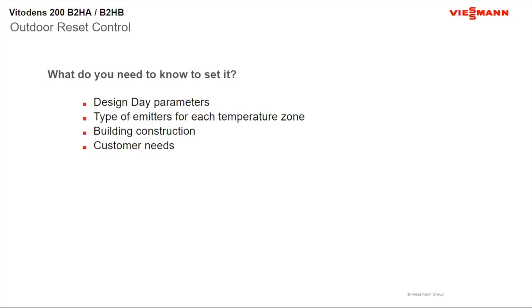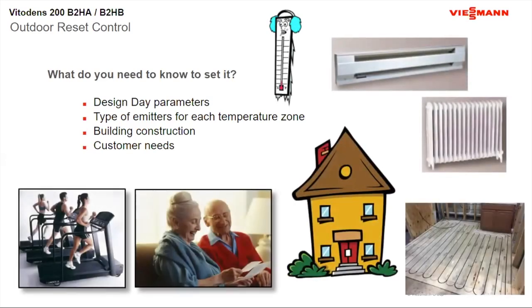The design day parameters to consider: what was the house originally designed for — or for new construction, what do your state requirements say? What type of emitters are you using and what supply temperatures will you need? Looking at baseboard manufacturer rating charts, temperatures go down to 118°F — you can heat a house with 118°F water if you have enough baseboard. What's the construction of the building, insulation levels? And customer needs — who's living in the house? The elderly don't sense temperature as well due to less moisture in the skin, so adding humidity to an elderly person's home will help them sense temperature better.